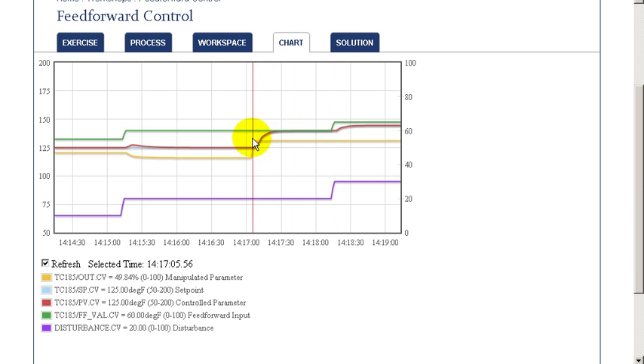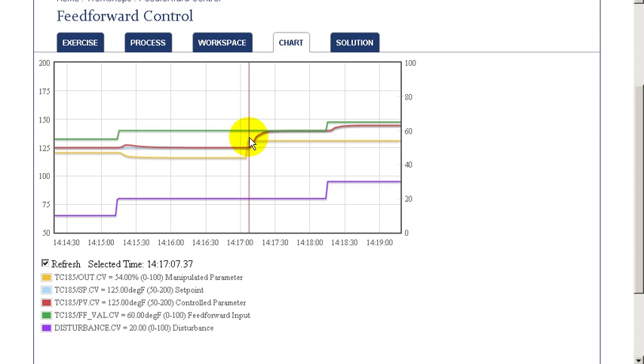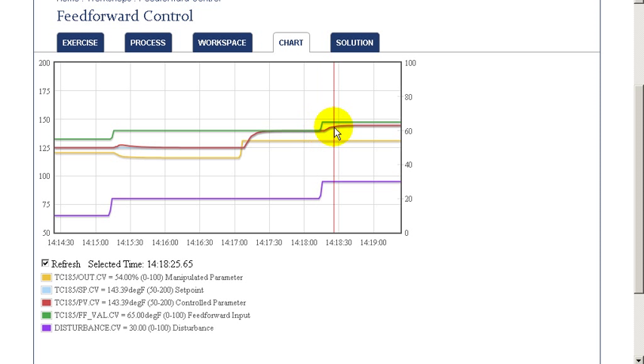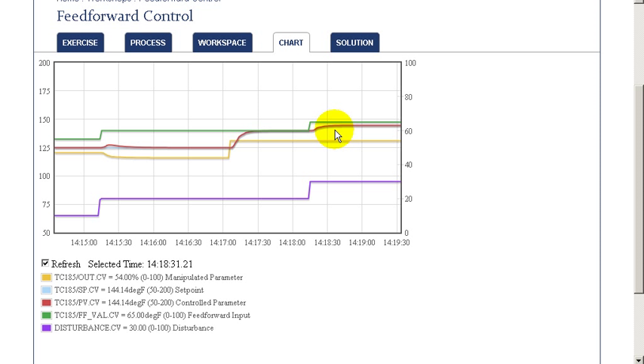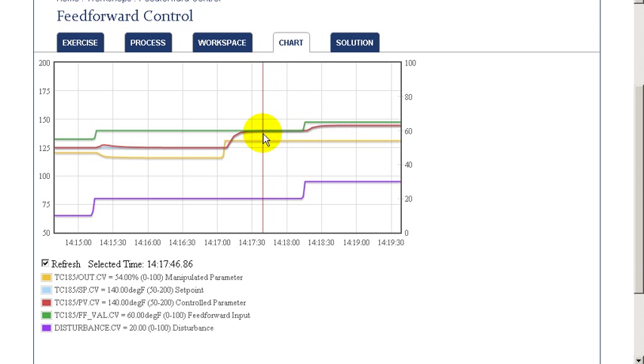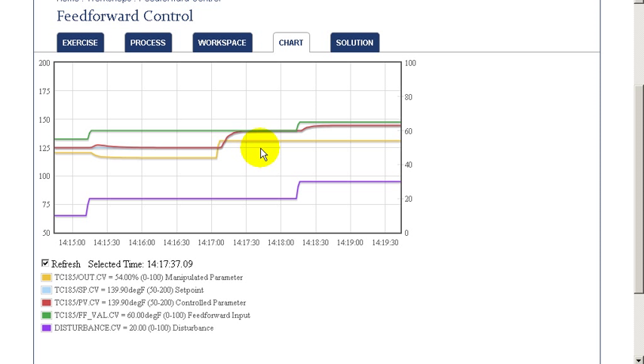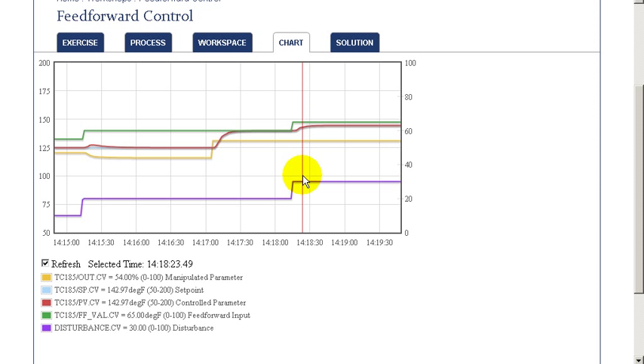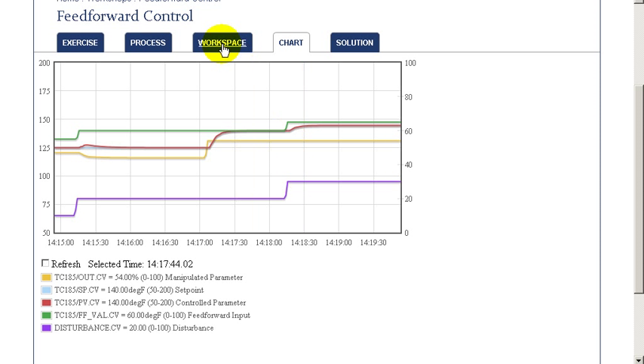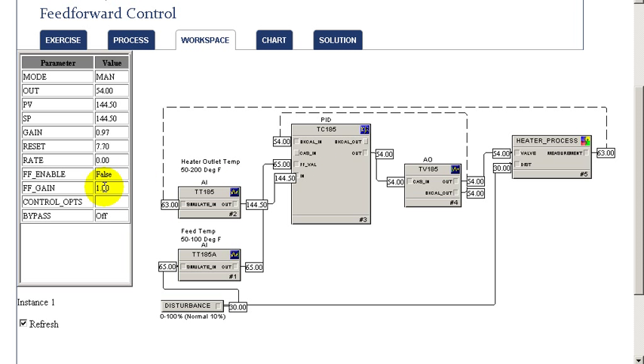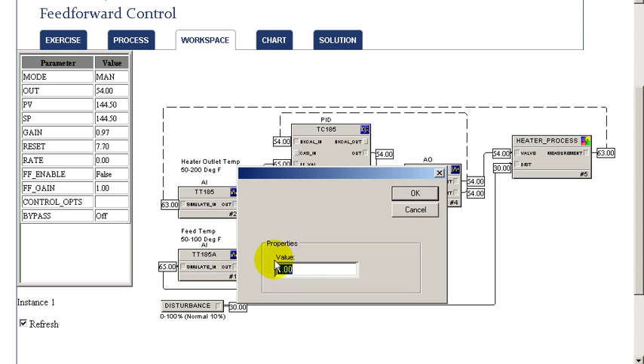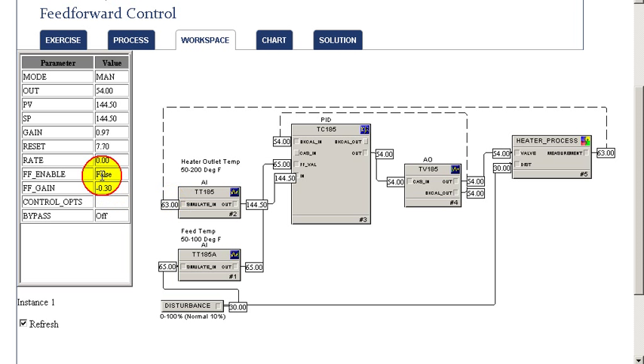In examining this response and the response to our steam valve, we see that the dead time and time constant associated with each response are about equal. So all we need in our feedforward is a feedforward gain — there's no need for a lead-lag or a dead time block. By looking at the magnitude of the change in output over the change in the manipulated variable as well as the disturbance, we can calculate the gain. The gain associated with our manipulated parameter is 1, and the gain associated with our measured disturbance is about 0.3. Therefore, the feedforward gain should be 0.3 divided by 1, negated — so our feedforward gain should be minus 0.3.